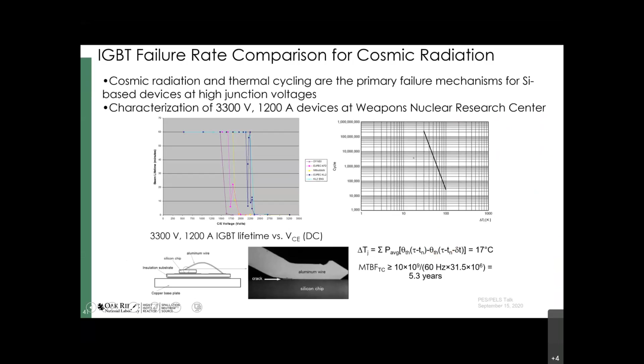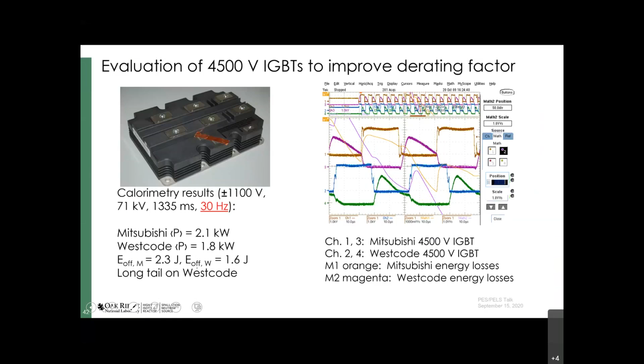So we looked at a 4,500 volt device, and this was a drop-in replacement basically for us, so the packaging was quite attractive, but these higher voltage devices have much poorer switching losses in this application. And in particular, the Westcode device had quite a long collector current tail as well. So these switching losses shown over here are actually at 30 hertz. These are comparable to the switching losses that we see at 60 hertz with our current 3,300 volt, 1,200 amp devices. So that didn't really look very encouraging.